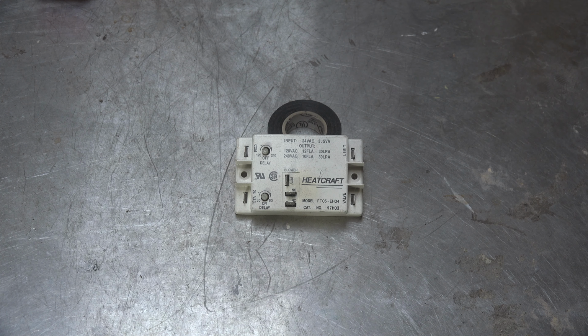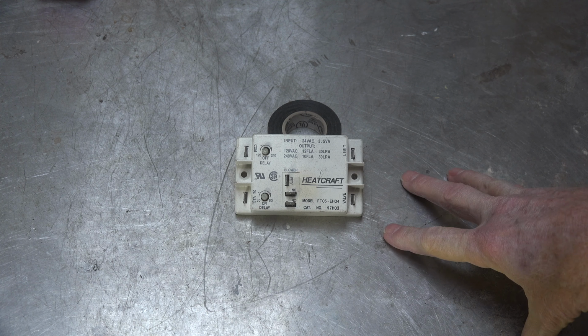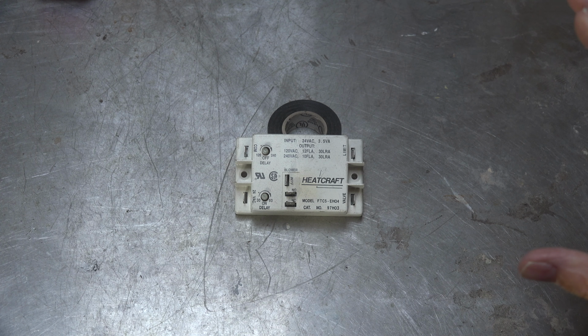I had a question the other day about one of these things. Now, this is a timer. It was used kind of commonly between ignition controls and integrated furnace controls when we had a lot of separate components and we were getting away from heat-operated fan switches. That's what this is: an electronic control to turn the fan on after the burner starts and shut the fan off after the burner shuts off. And it's a timer. That's all it is.